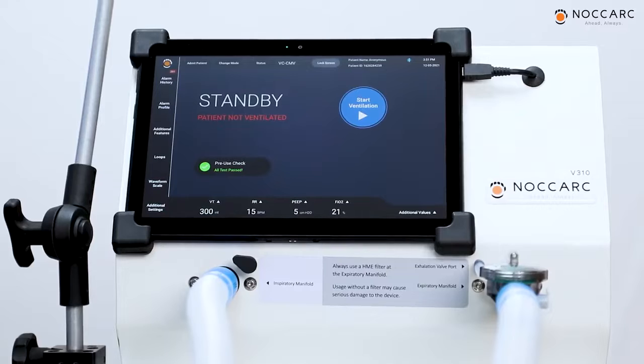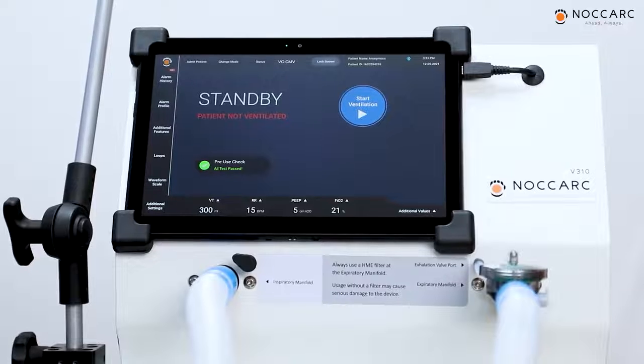In this video, we are going to perform pre-use check on Noccarc V310. Pre-use check is a short and simple sequence of tests that verifies proper operation of ventilator hardware and performs sensor calibration. Before performing the test, we have to ensure that patient is not connected to the ventilator and all the HME filters connected to the ventilator should be removed. To start pre-use check, press on this pre-use button and follow the instructions coming on the screen. First instruction is please turn off the oxygen supply.